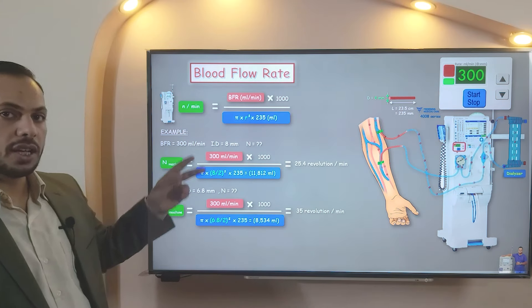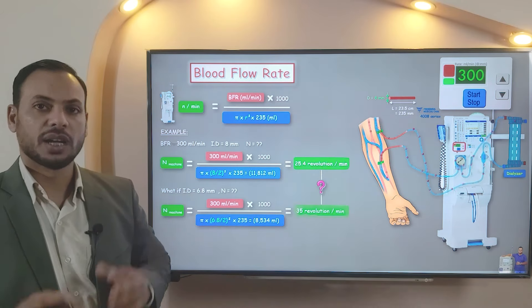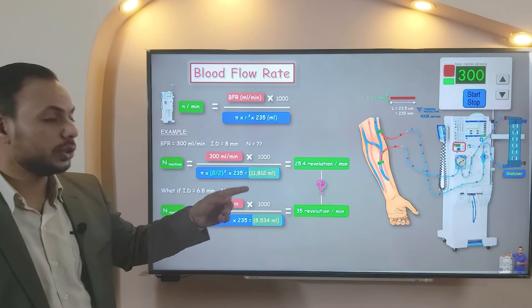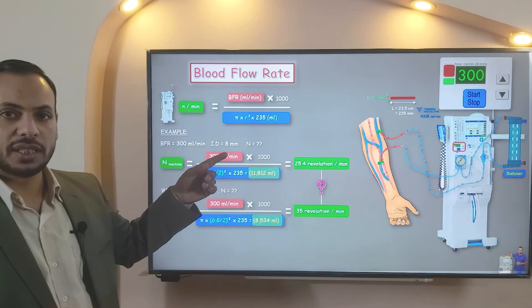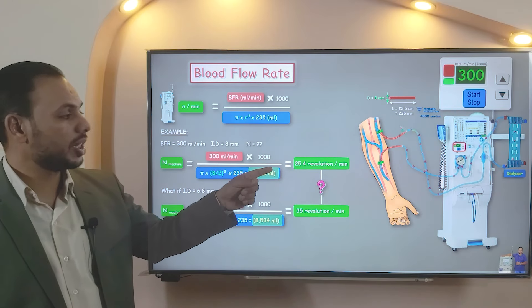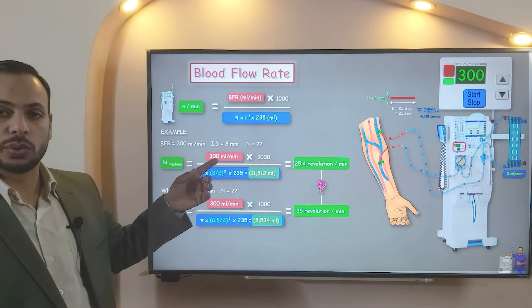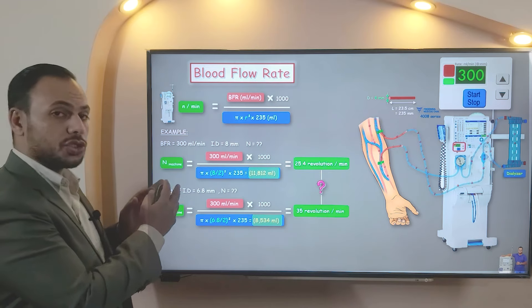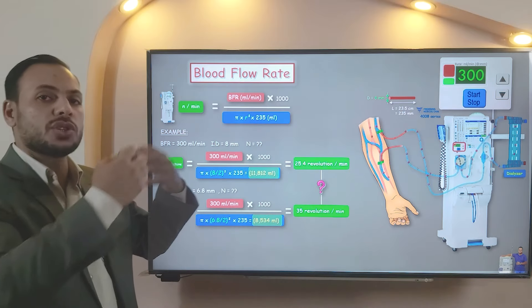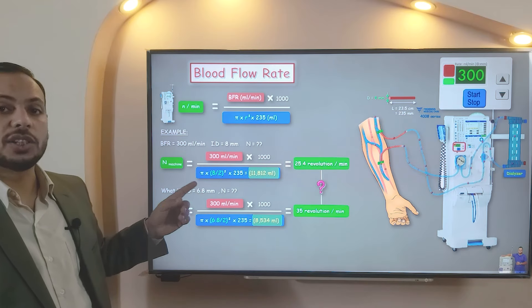We have the same blood flow rate but a different number of revolutions per minute. Why? Simply because we have different stroke volumes. The stroke volume varies according to the internal diameter. If the internal diameter increases, the stroke volume increases, so the machine will minimize the number of rounds to achieve the targeted blood flow rate — and vice versa. When the internal diameter decreases, the stroke volume decreases and the machine needs to run more rounds to achieve the targeted blood flow rate. So, please take care of the internal diameter.